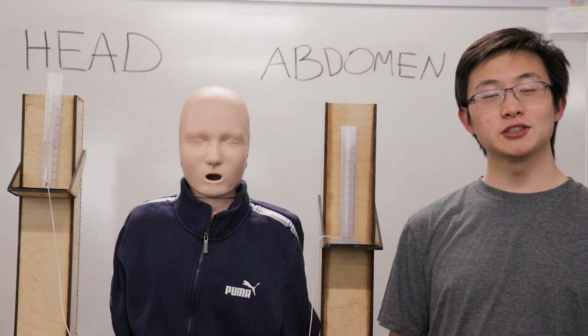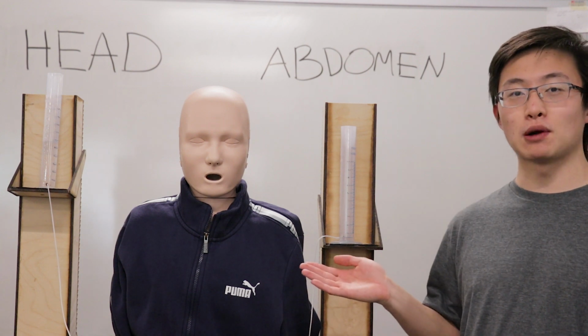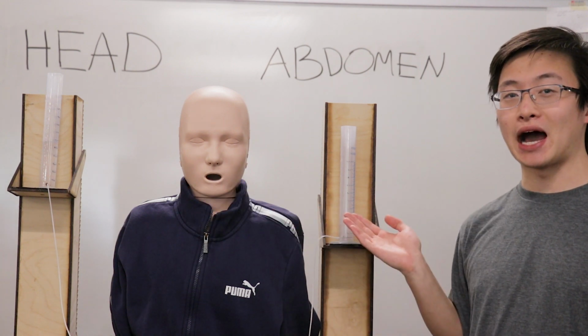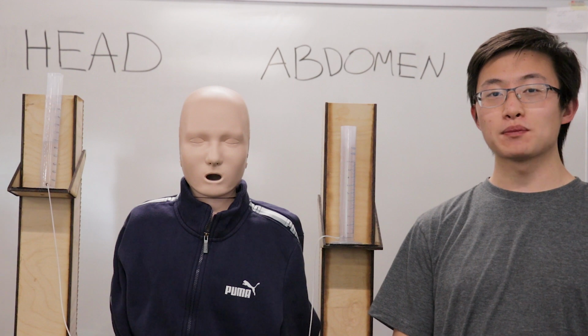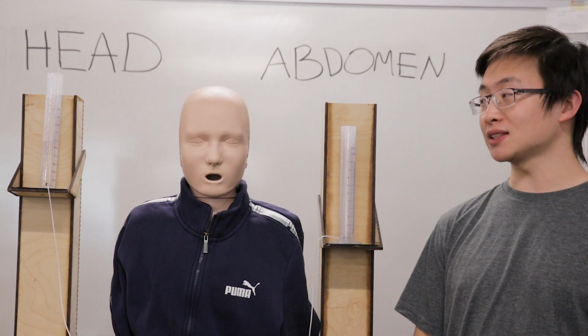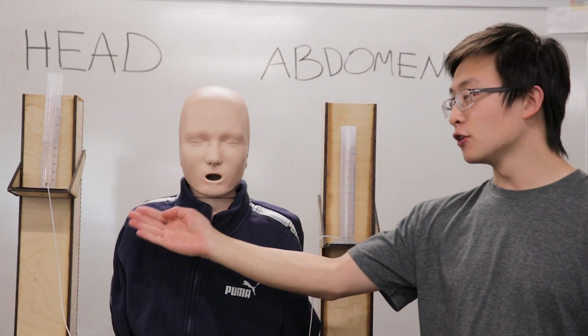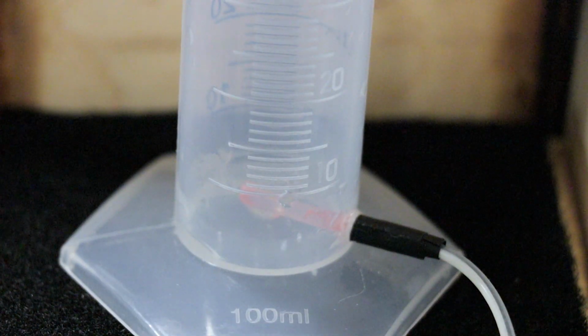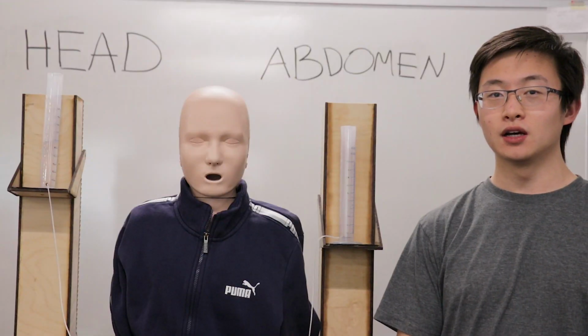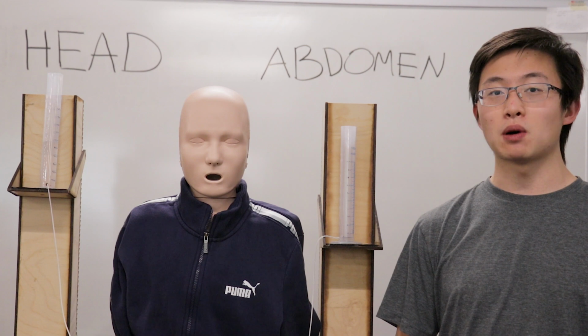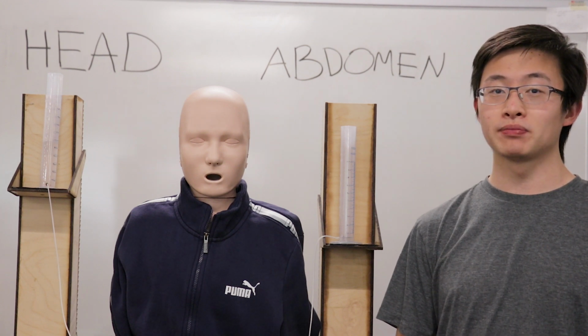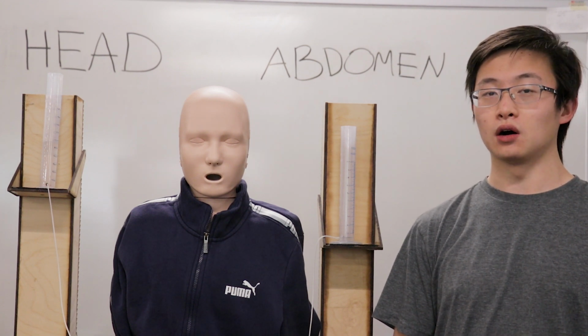To help visualize how shunts work, we have set up this test stand to represent the pressures in the head and the abdomen. Fluids always flow from a high pressure to low pressure, so in this case, fluid will flow out of the head through the shunt tubing and into the abdomen following a positive pressure gradient. Shunts operate under the assumption that this positive pressure gradient is always there. However, this assumption is not always valid.